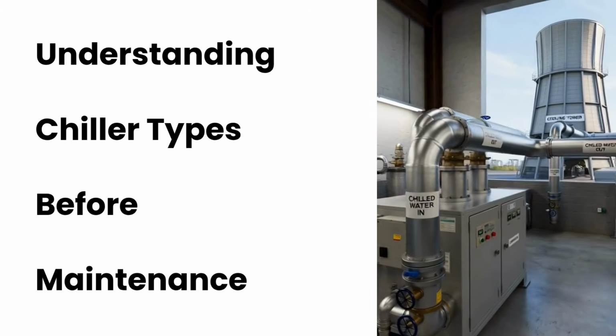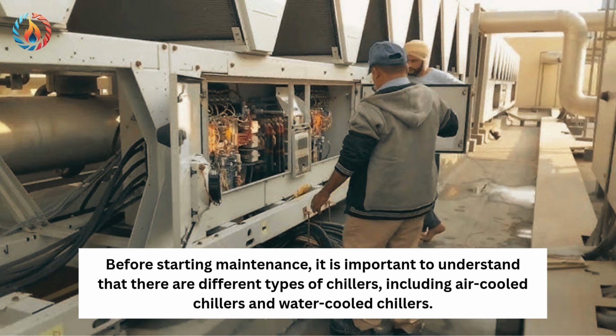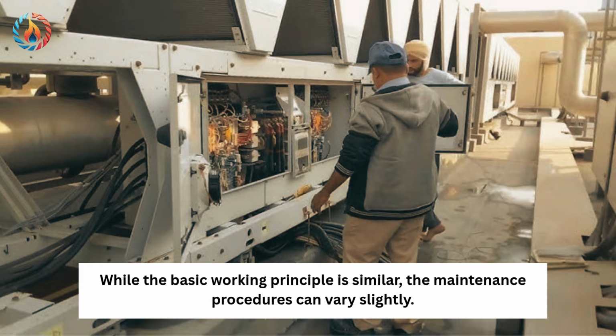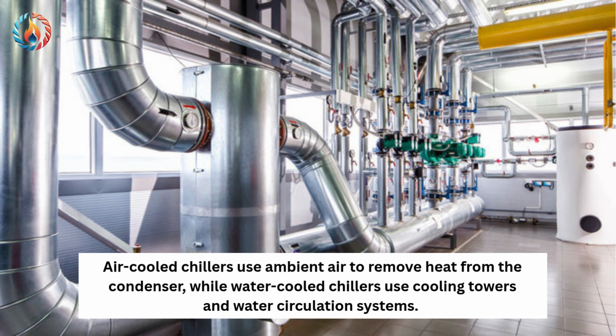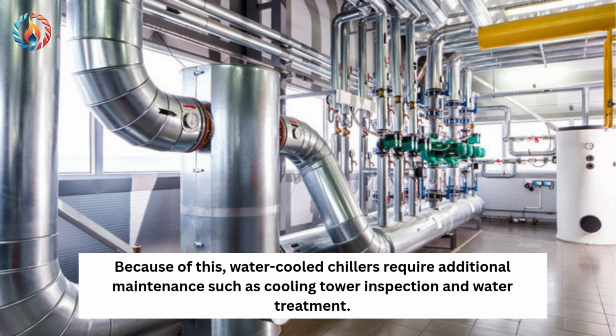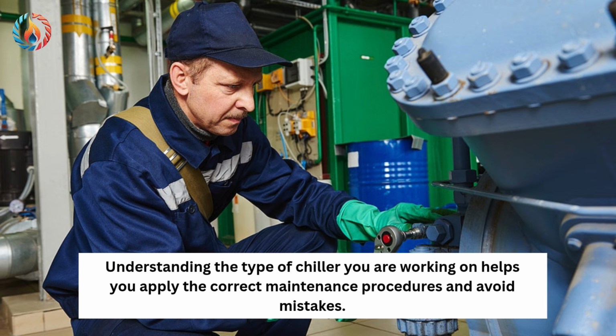Understanding chiller types before maintenance. Before starting maintenance, it is important to understand that there are different types of chillers, including air-cooled chillers and water-cooled chillers. While the basic working principle is similar, the maintenance procedures can vary slightly. Air-cooled chillers use ambient air to remove heat from the condenser, while water-cooled chillers use cooling towers and water circulation systems. Because of this, water-cooled chillers require additional maintenance such as cooling tower inspection and water treatment. Understanding the type of chiller you are working on helps you apply the correct maintenance procedures and avoid mistakes.